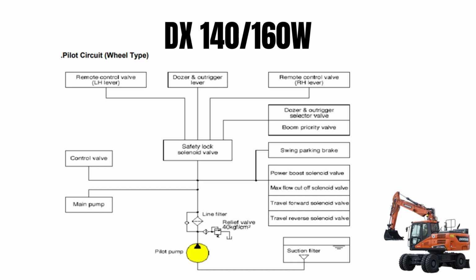Pilot pump gets the oil from this hydraulic tank through suction filter. There is suction filter inside the hydraulic tank. This is mesh type, screen type suction filters, and it prevents the metal particles from getting inside the hydraulic intake line or suction lines.